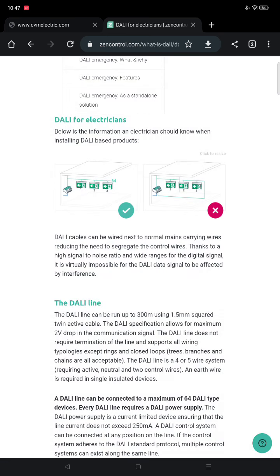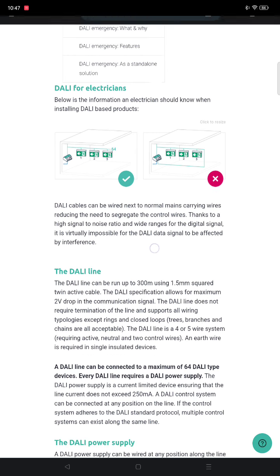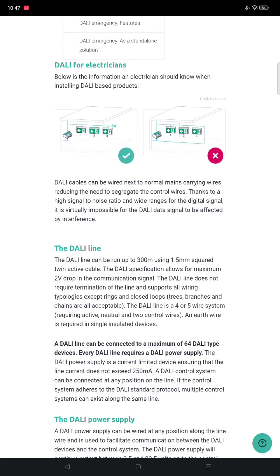So, a DALI cable can be wired next to normal mains-carrying wires, which reduces the need to segregate the control wires, thanks to a high signal-to-noise ratio and a wide range for the DALI signals. It is virtually impossible for DALI data signals to be affected by interference.